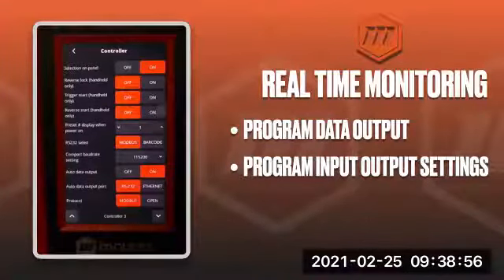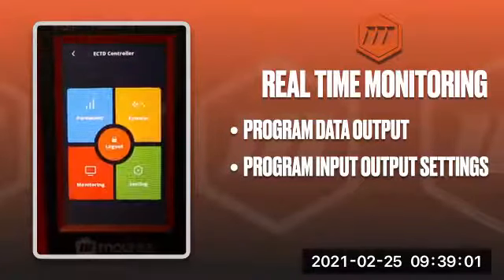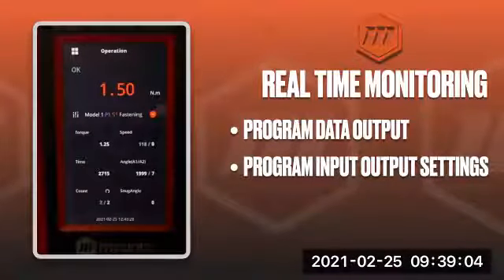We can also turn on our SD card as well, and any torque data that we go ahead and run, we're going to be able to capture the time, the date, the preset that was used, the preset target, the actual torque that was delivered, the total amount of angle, also the total amount of time in milliseconds. If there was a fastening error, we would be able to get that information. If there is a preset change, we'll see that information.